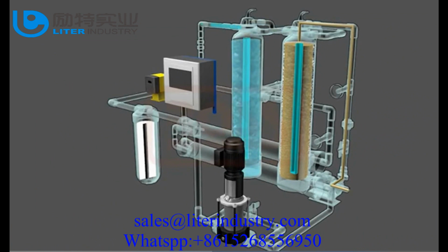Antiscalant is then dosed in water with the help of a doser to avoid scaling on membranes. Water is further passed to a micron cartridge filter for fine filtration. Water is then pumped by a high-pressure pump into the RO membranes.